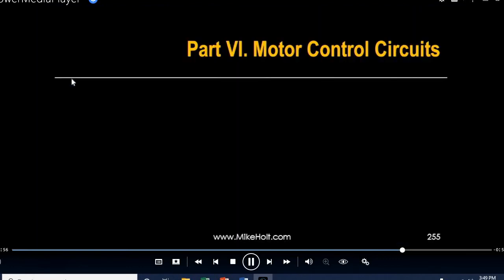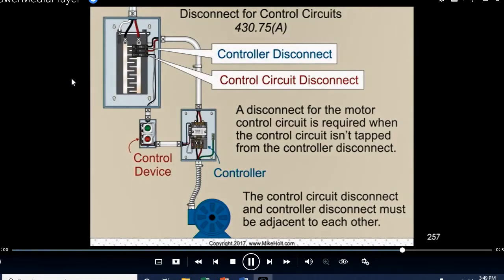Motor control circuits. A disconnect for the control circuit. A disconnect for the motor control circuit is required where the control circuit isn't tapped from the controller disconnect. In other words, if you're running a control circuit to your controller, so where's my control circuit? Oh, right here. Here's my control circuit. Well, then I need to have a disconnect for that control circuit, and it must be adjacent to the controller.